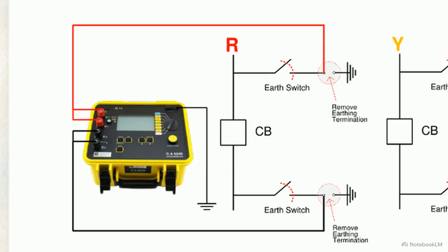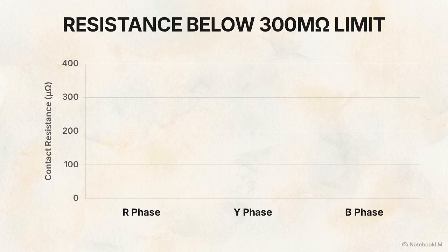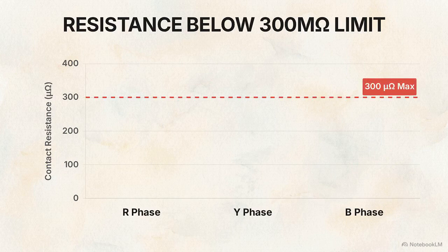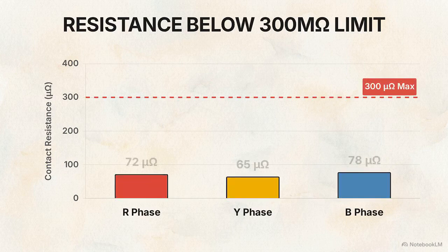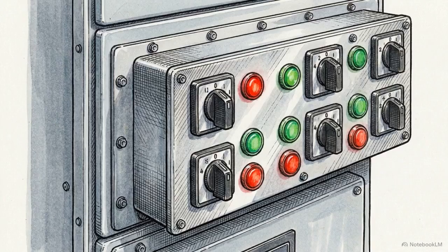Moving to the contact resistance test, this schematic shows the setup designed to push high current directly across the closed main contacts. The instrument injects 100 amps DC across the path, recording the voltage drop to calculate exact resistance in microohms. Achieving a contact resistance below 300 microohms across all 3 phases confirms the breaker can safely carry grid-level current without overheating. Once static integrity is verified, we test the breaker's dynamic mechanical operation and control logic.